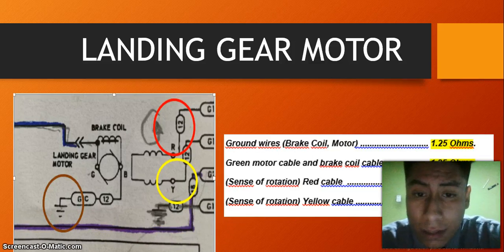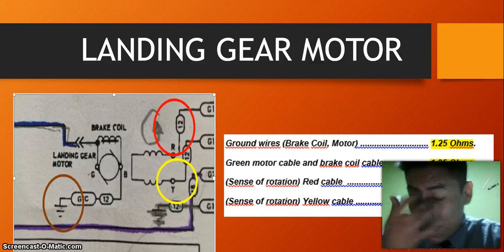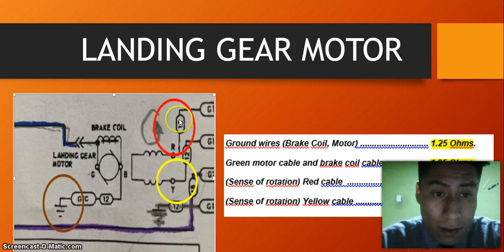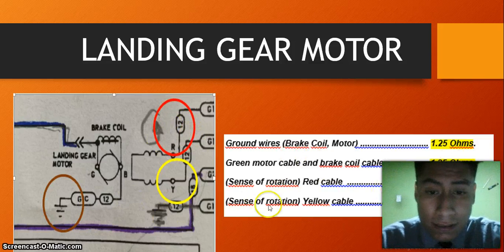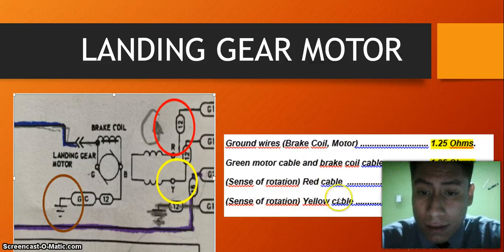Coil measurements, in addition to the turning points, obtained the following results: the ground wires and brake coil motor measured 1.25 ohms. The green motor cable and the brake coil cable measured 1.25 ohms. The red cable of the motor, for sense of rotation, measured 2.6 ohms, and the yellow cable, for sense of rotation, also measured 2.6 ohms.